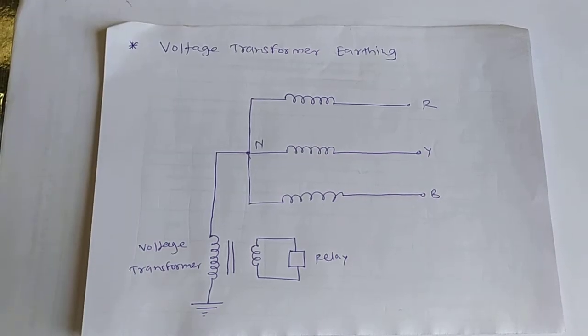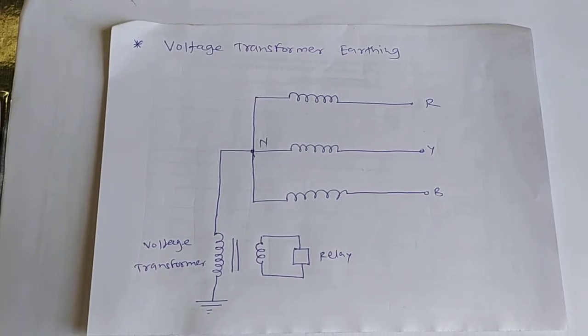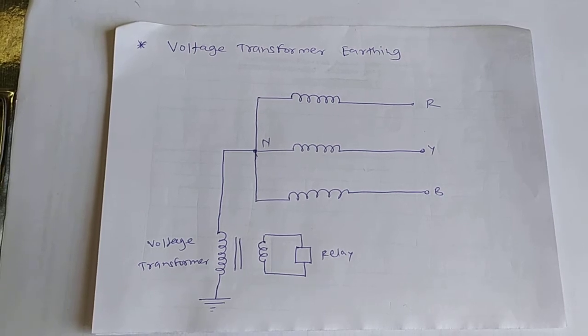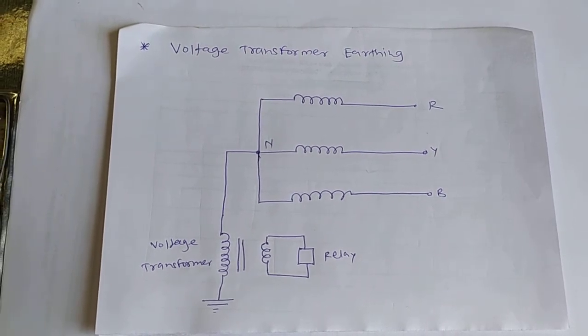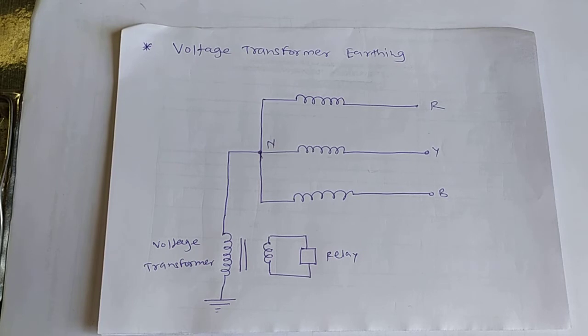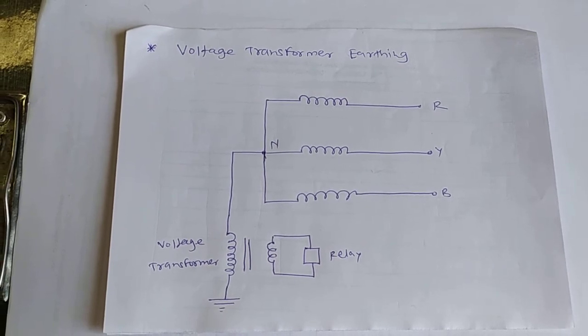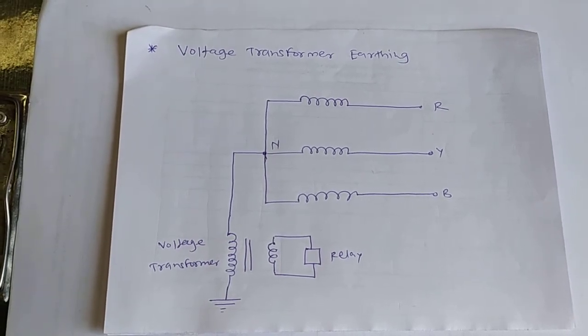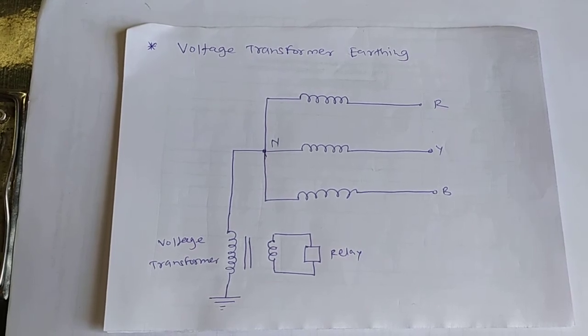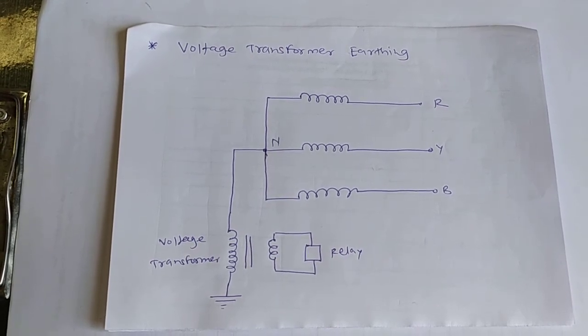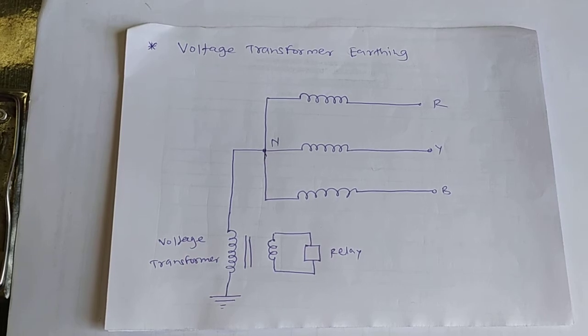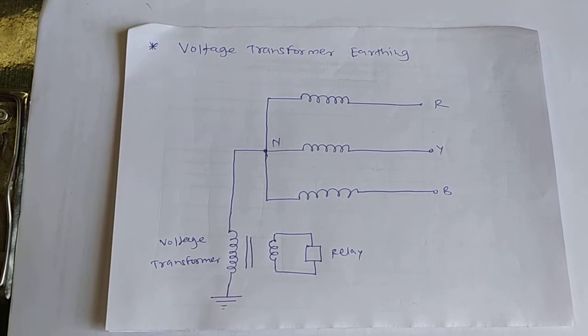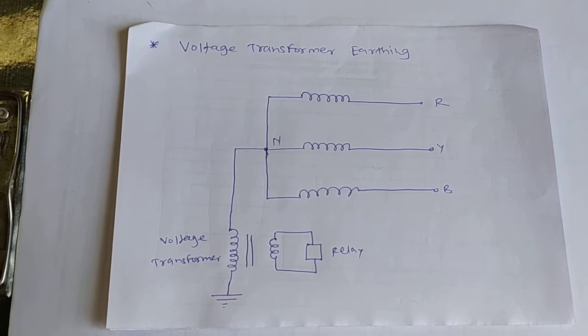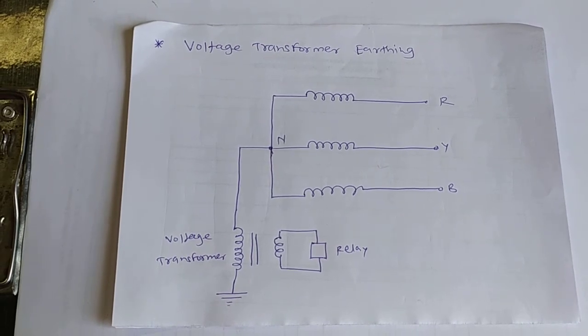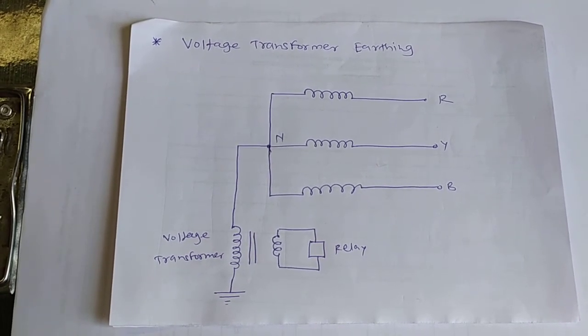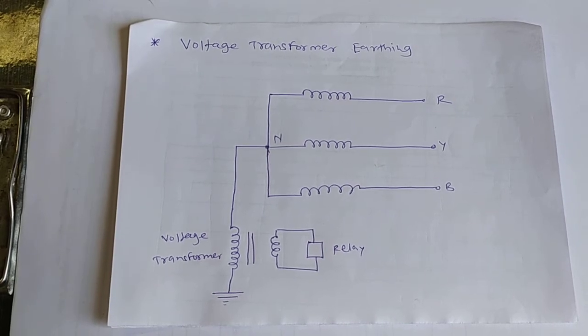Voltage transformer earthing. In this method of neutral earthing, the primary of a single phase voltage transformer is connected between the neutral and the earth. A low resistor in series with a relay is connected across the secondary of the voltage transformer. The voltage transformer provides a high reactance in the neutral earthing circuit and operates virtually as an ungrounded neutral system.